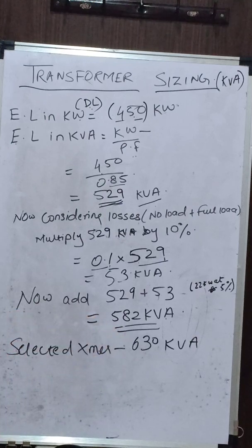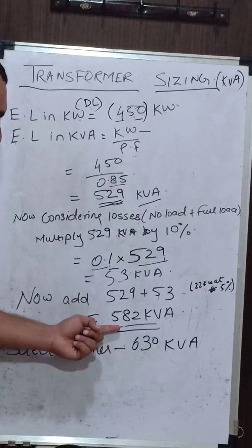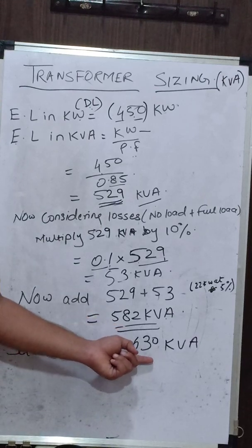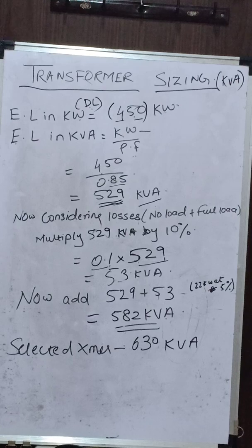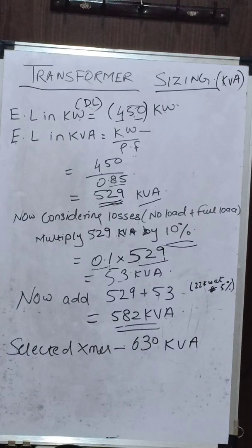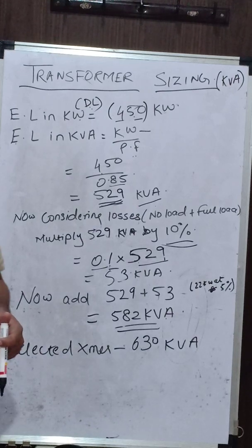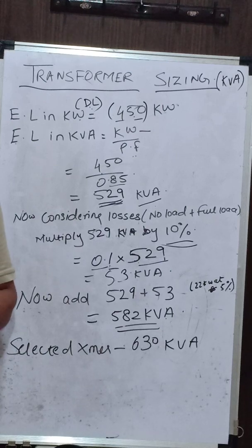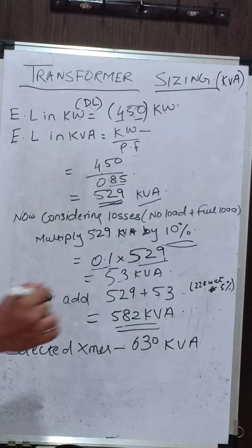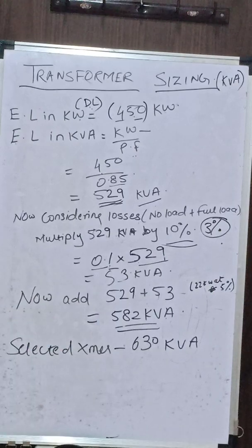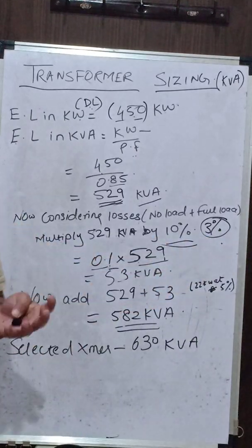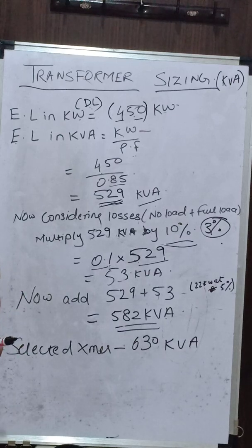Since 582 kVA is not a standard size, you select the nearest available standard transformer: 630 kVA. Regarding the 10% multiplier — as per the Energy Conservation Building Code and Indian Standards IS 11180 and IS 11171, the internal losses (no-load and full-load) of any transformer shall not exceed 3%. So by multiplying by 10%, we are being conservative — only 3% is consumed by transformer losses.